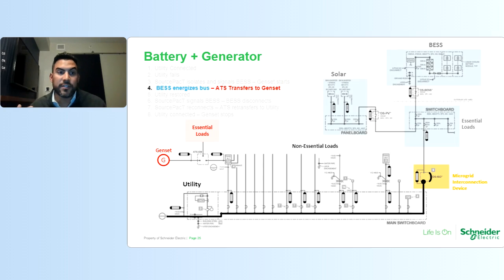That energy storage system comes online, where it's now providing power to those essential loads in your facility. Again, we've isolated those in that critical panel board, as well as the solar system. So if you're looking to use your solar system in parallel with the battery, perhaps you can downsize the energy storage system and use it in parallel with the solar to add additional capacity. There are different ways to design your system here. In this design, the client wanted to use both battery energy storage and solar for emergency power. While remaining disconnected from the grid, the ATS transfers from utility to generator, providing power to its own essential loads.